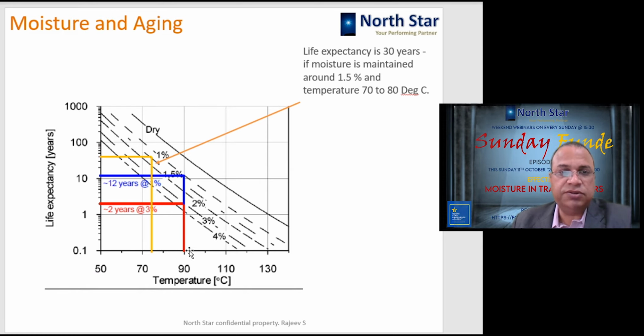So let us look at a situation over the red line. This particular transformer is operating at 90 degrees centigrade, and it has 3% moisture in it. With 3%, which is almost very wet, the transformer will not serve more than 2 years. If we dry this transformer out and bring the moisture level to say 1%, then instead of 2 years it can work till 12 years. So 10 more years of life getting added here.